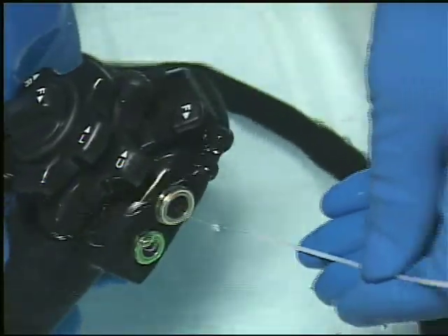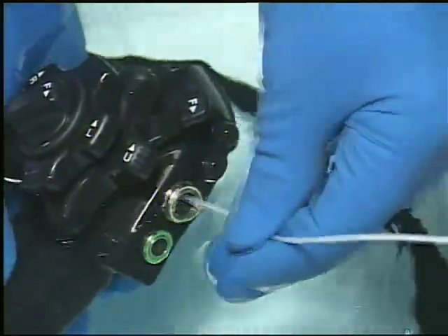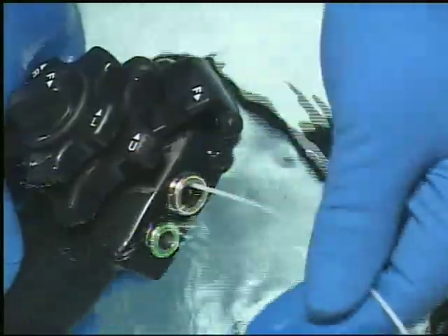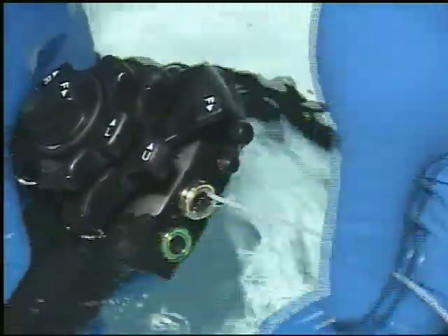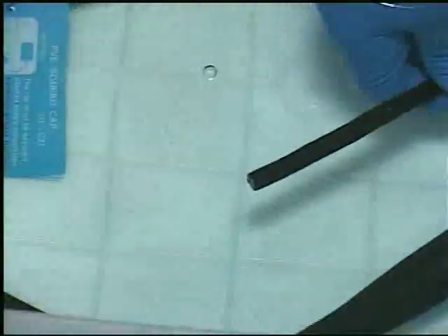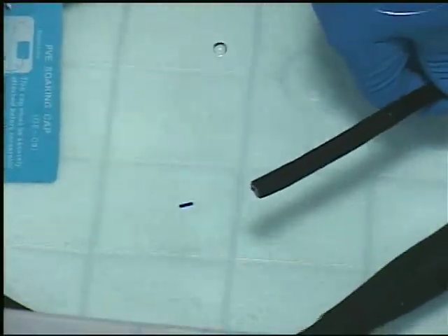Insert the blue-coated end of the cleaning brush CS6021T into the opening at the bottom of the suction control valve receptacle on the control head and gently advance until it exits the distal tip of the scope.